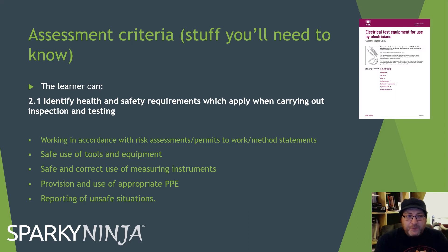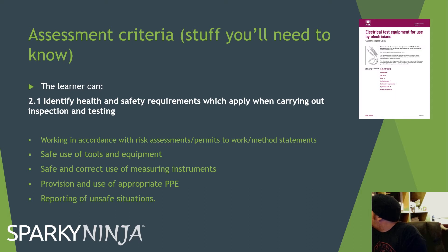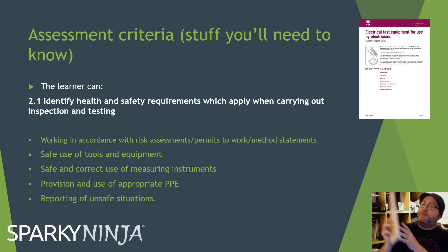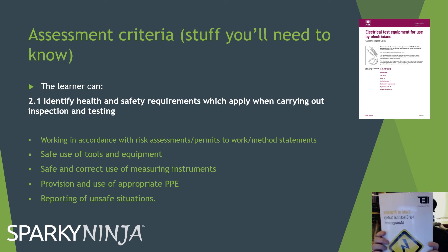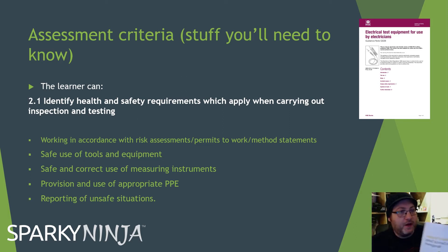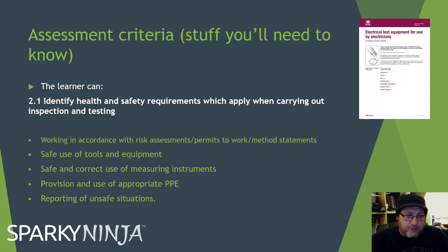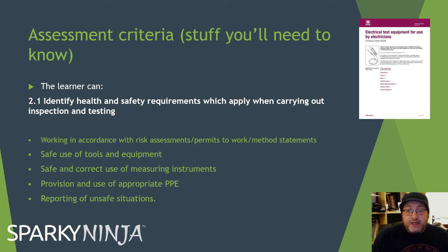You need to develop a happy equilibrium where you've satisfied the PPE requirement for the environment. On a construction site, there's PPE for that environment; in domestic settings it's less risky. From an electrical perspective, PPE would mainly be eye protection if there's a risk of arc flash, and gloves maybe. The Code of Practice for Electrical Safety Management covers a good understanding of live working and the hierarchy of controls, with PPE right at the bottom — since all inspection and testing work is essentially live work, unless you're only doing continuity measurement.